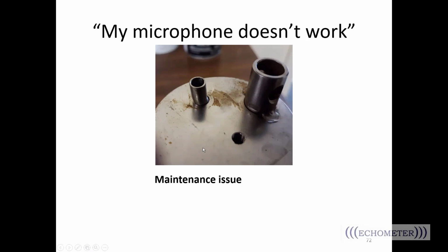Yes, this customer called in and he said, hey, I'm not having any response on my microphone. So I had him check it, and I said, I did the bump test and he's not having any response at all. So I had him send it to us for repair. And this is what happened. I think they were trying to remove the microphone. And if you look at it closely on the electrical tube, you'll see like a small nut. So I think what happened was the microphone protector was heavily rusted, where you're gonna see it in a couple of minutes here.